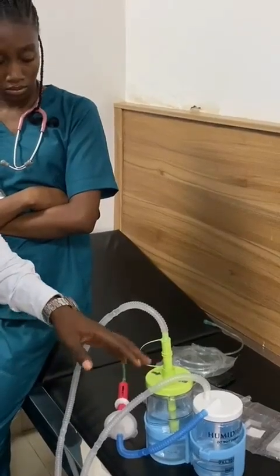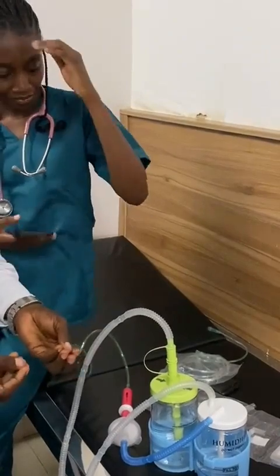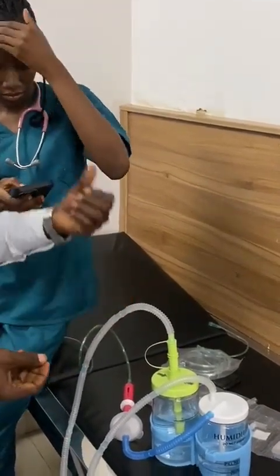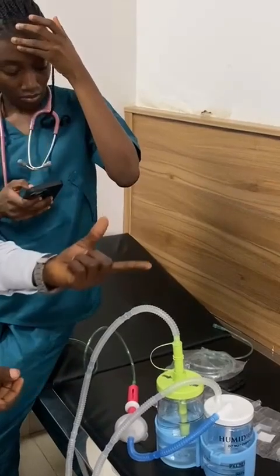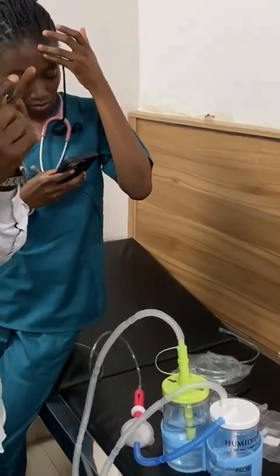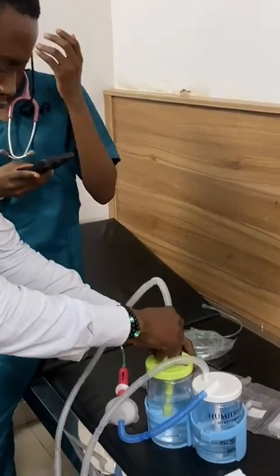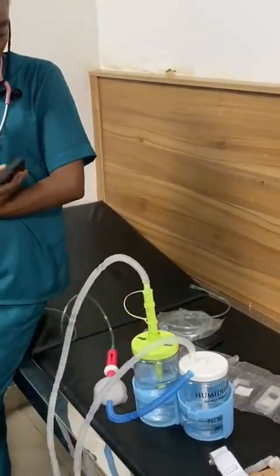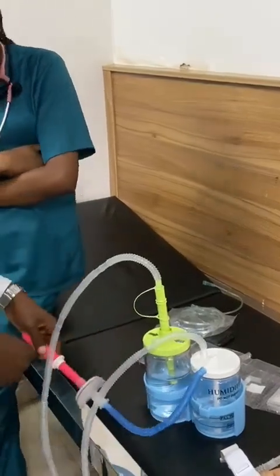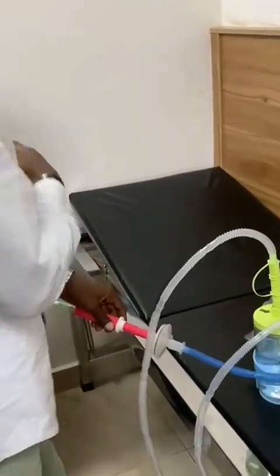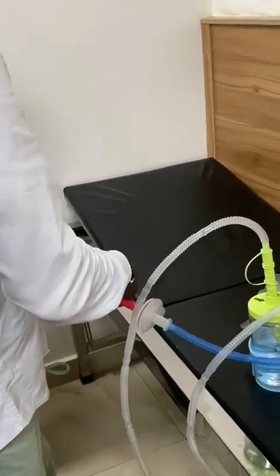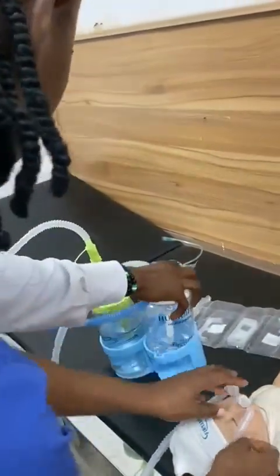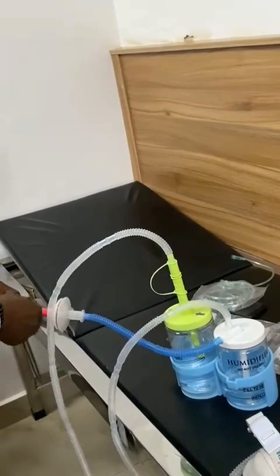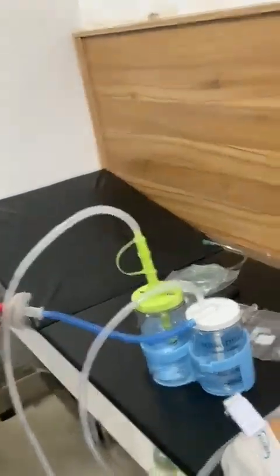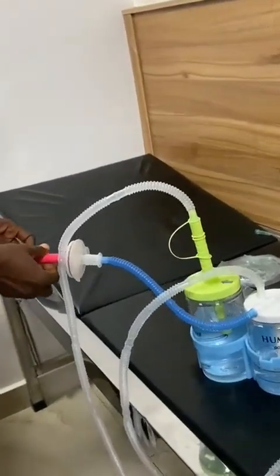So if the patient requires, let's say, 8 centimeters of water pressure, that means your flow rate too will be high, so that you can drive the pressure. So just adjust to correspond. Now if this is not around the body, take the flow as high as possible. This one is not even getting here at all. Yours should be bubbling. It's bubbling, it's just not very strong. So increase the oxygen flow. This one is not connected.